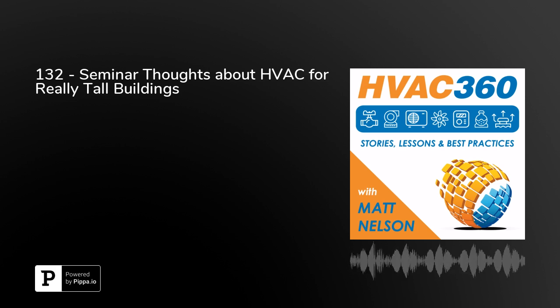So even at the ground floors, where you'd never consider freezing conditions because they just don't happen, way up at the top you really do have to account for freezing conditions in your design. They do change like that. So one of the pluses is that you get basically free cooling, or it would cost less to cool the upper spaces. But you do end up paying more because of the fan energy and the pump energy, because of the height. The fan energy, because the air is less dense. So those are some of the trade-offs going from ground level to up high.